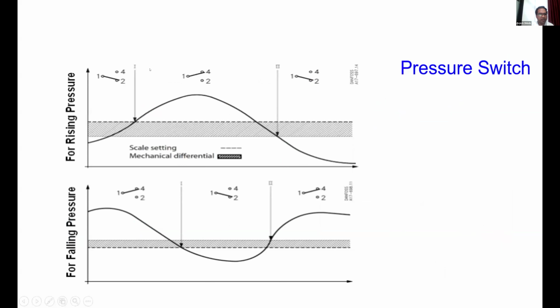We can see here in this diagram. I will try to explain this diagram. You can see this is the pressure on the y-axis, and here is the x-axis, and this is the set point you can consider. Now suppose, for example, the set point is 30 bar. What will happen? In this graph, we can see that till 30 bar, the contacts are connected to terminal number 2. It means this is the NC terminal, that is the normally closed terminal.